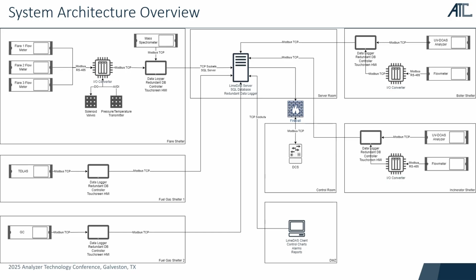And when we're talking about controlling solenoid valves, we have a digital output. So it's going the other way. We're sending a Modbus signal to the converter, and that energizes various valves. And so all of that goes into the central data collection unit, which typically resides on a Class 1 Div 2 for this application hardware, a ruggedized PC that also has a touch screen on it, so it can work both as a buffer for many, many years with modern hard drives. It can be a controller that controls all the solenoid valve interlocks and NAD logic and calibration, purge, etc. And it also buffers all the data and then sends it to the central DAS server over a local area network through using TCP sockets.